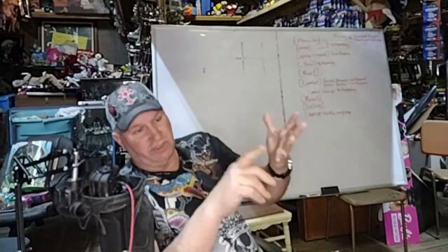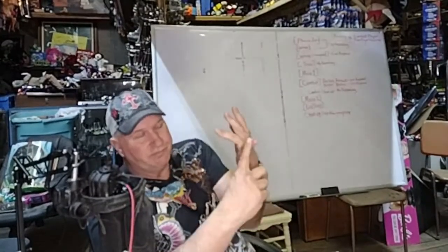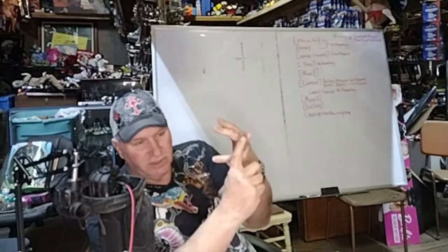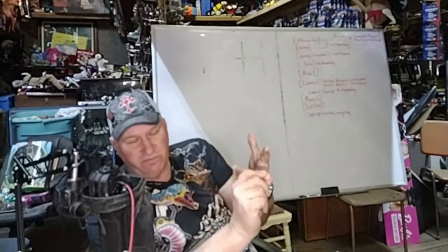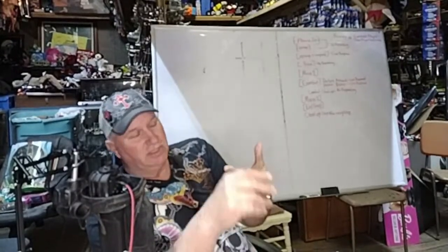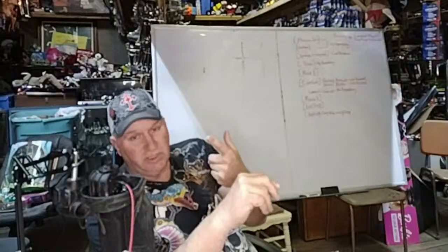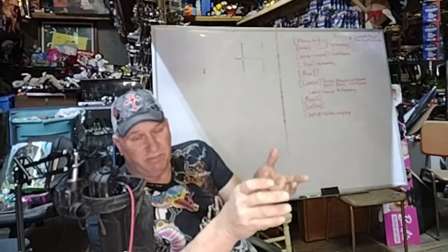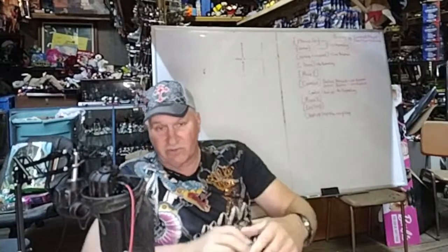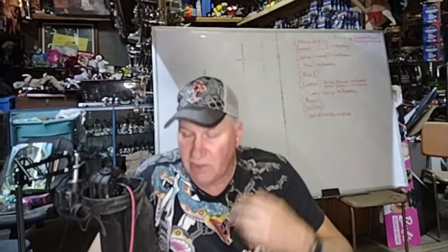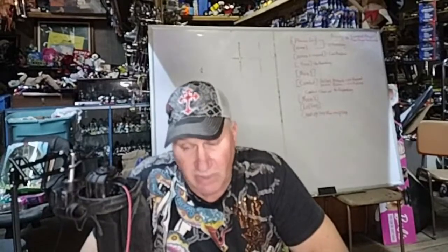So there's your 4 things: the crossover ductwork, something in the vent, closing down your vents a little at a time, and make sure you got return air. There is no ductwork like in a house where you got a duct that pulls return air out of that room. It's going to come underneath the door back to the unit, and then either make it a little bit colder or a little bit warmer depending on the season. So there's your 4 things. That's what I suggest. That's what I've seen over and over.